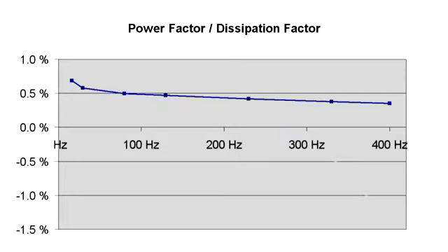This is what the curve looks like after the contacts have been cleaned and the bushings were connected to each other. Bad contacts can result in a measured dissipation factor far better than the actual value, which will lead to a completely wrong diagnosis. To make sure that the measurement itself is in order, it is important to record frequency responses.